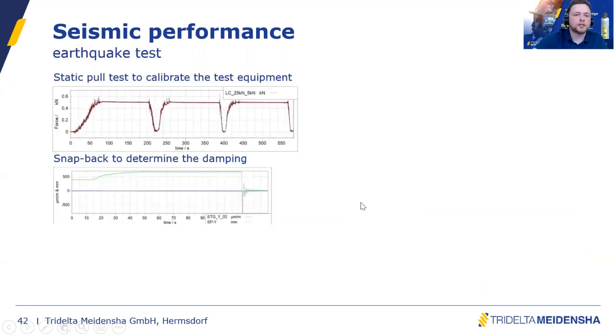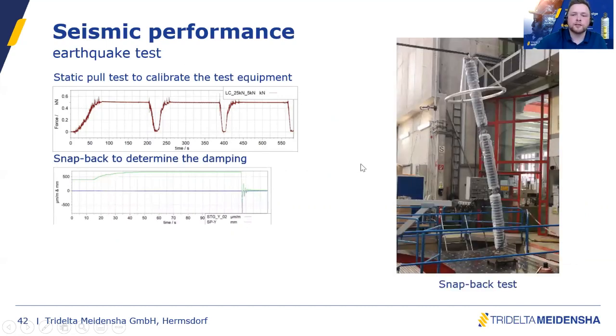The earthquake test consists of 3 steps. We have a static pull test to calibrate the test equipment. So we pull on the surge arrestor. It looks like this. You see how this surge arrestor is bent under the strong force of the pull test. And then we release it and the surge arrestor will snap back. That's why it's called the snap back test. When an impulse like this is applied to a mechanical system, it will swing in its natural frequency and you will see the damping behavior. So you have this downwards curve, this oscillation going down. So this is what we have to do as the second step.